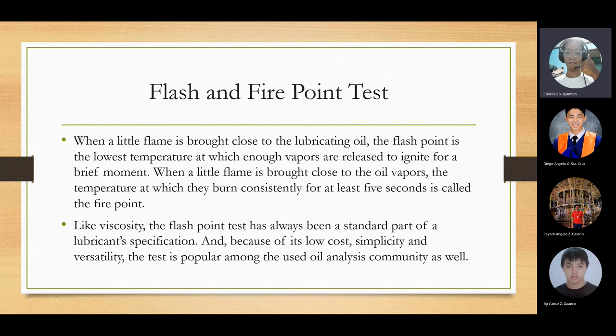Flash and fire point test: when a little flame is brought close to the lubricating oil, the flashpoint is the lowest temperature at which enough vapors are released to ignite for a brief moment. When a little flame is brought close to the oil vapors, the temperature at which they burn consistently for at least five seconds is called the fire point. This test finds the temperature for brief ignition and the temperature for consistent burning of at least five seconds.